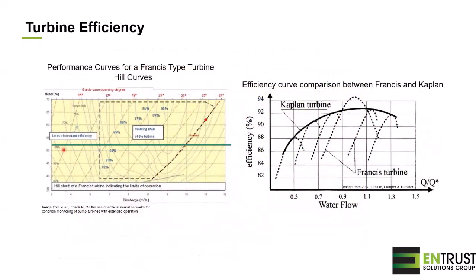If we take this same chart and go along this line for a certain head, we will find a power curve here, for example. These are all power curves for a Francis turbine operating at different flows, at different heads, sorry. And when we assemble all these Francis curves, we can compare that, for example, to a Kaplan turbine that will have a much more horizontal power curve. So we have more efficiency over a long range of flow as compared to a Francis turbine that will operate at peak efficiency only at a specific amount of flow. So this allows us to compare easily a Kaplan with a Francis turbine.